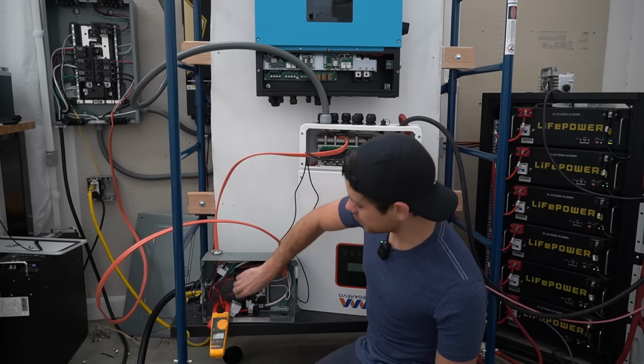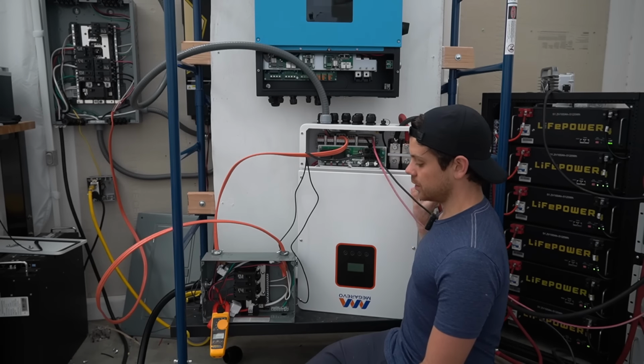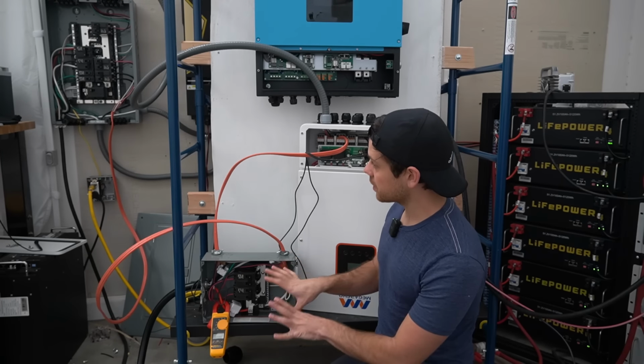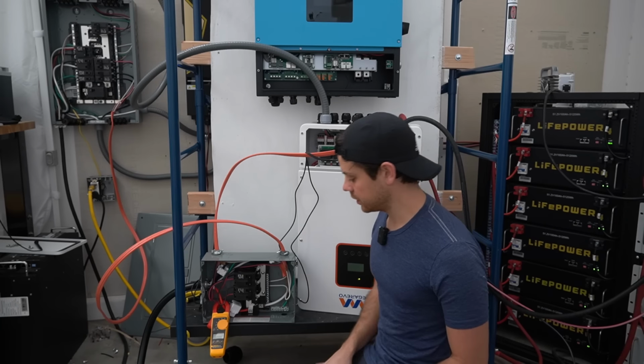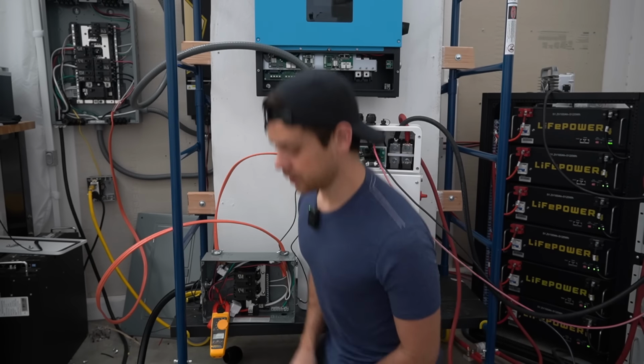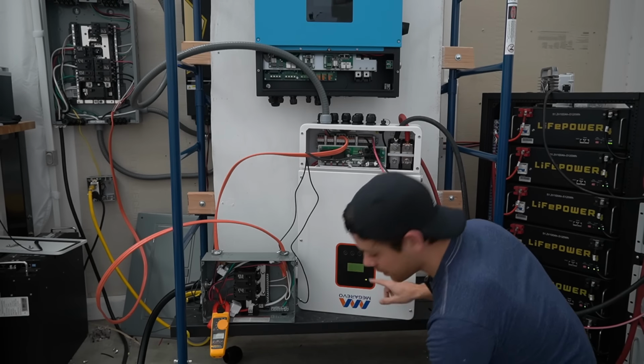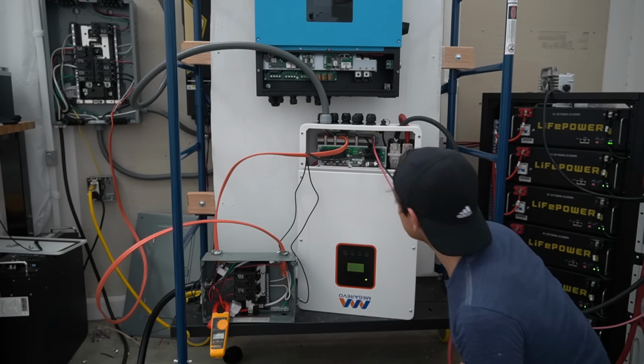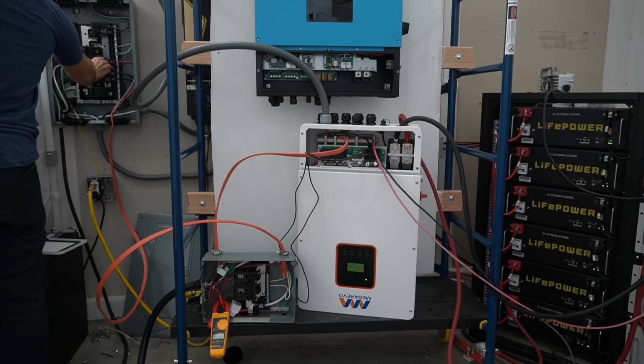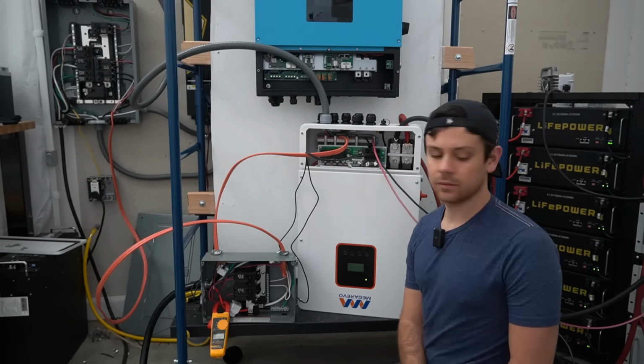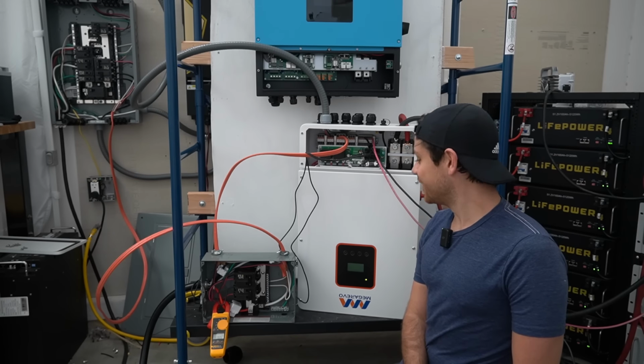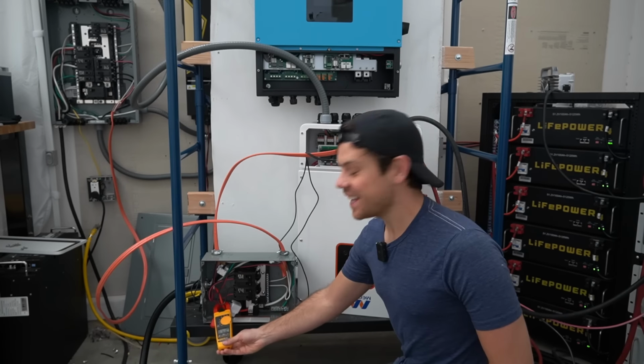And then we're gonna turn on the breakers. Then we're gonna turn on the inverter. Now we can't touch anything over here at all. It is high voltage. And then I'm gonna turn on the AC input. Oh, we have voltage. Everything seems to be working. Now we can add a load. And we should have power. There we go. And look at that, it's running the heat pump.